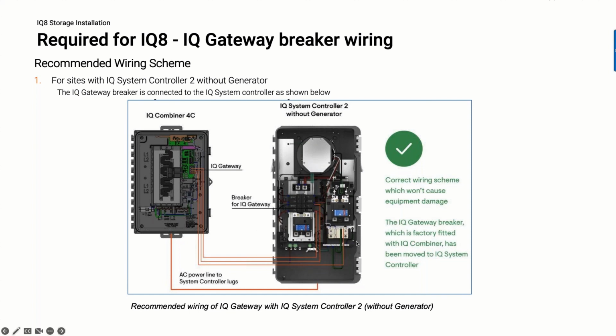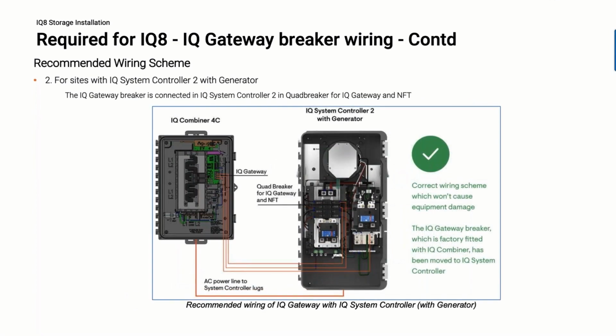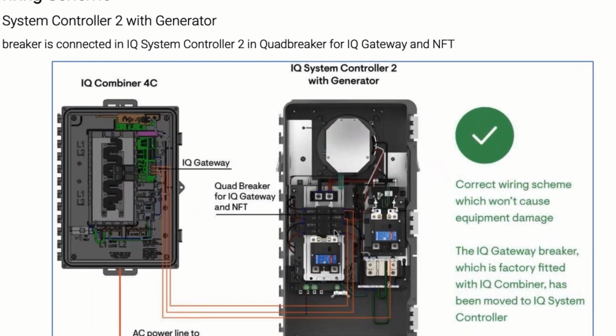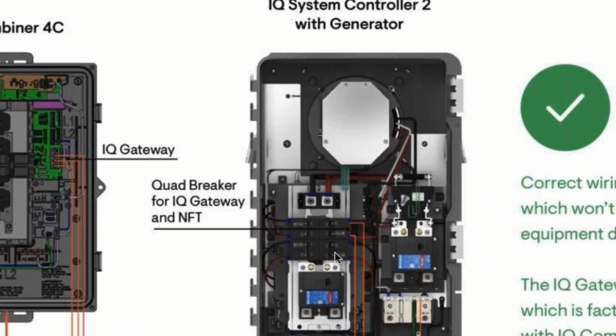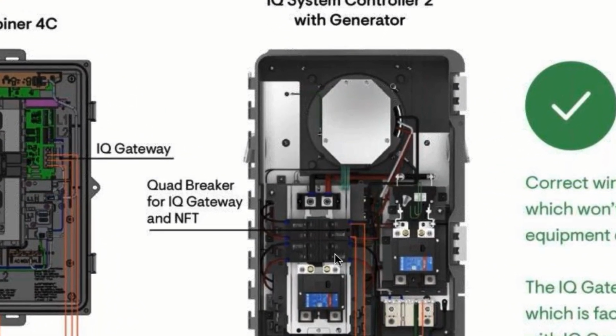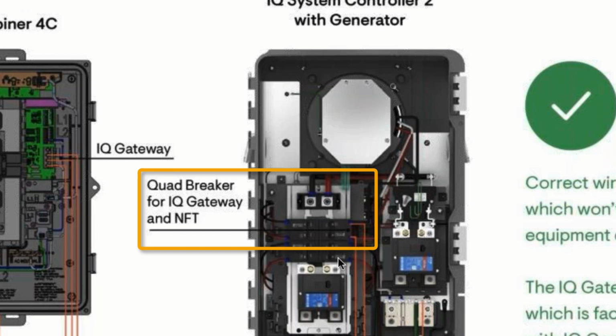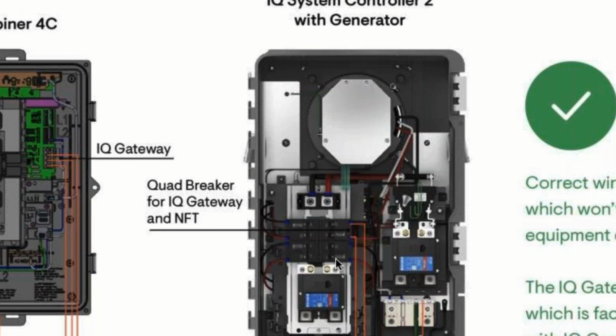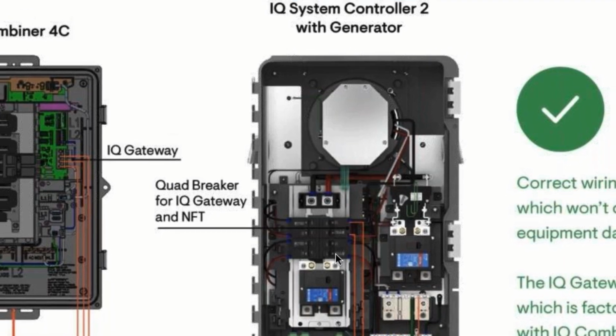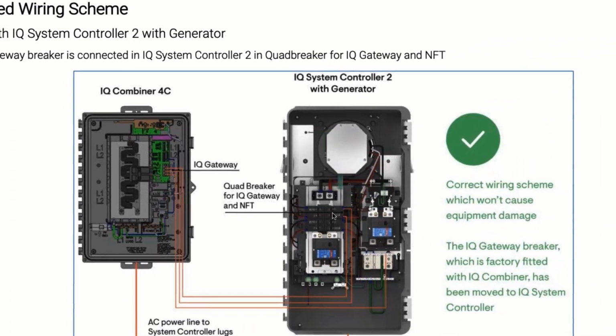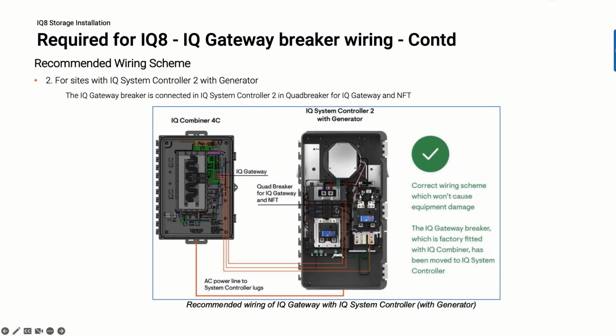If the generator slot is being reserved or used, a second method to power the IQ gateway directly from the system controller bus is to remove and replace the 40 amp neutral forming transformer, or NFT, breaker, and replace that with a 40/20 quad breaker. It's got to be an Eaton 40/20 quad. Using a quad breaker, wires connected to the 20 amp section of the quad breaker can be used to feed the IQ gateway, and then the 40 amp section of the quad breaker will be connected to the NFT breaker.